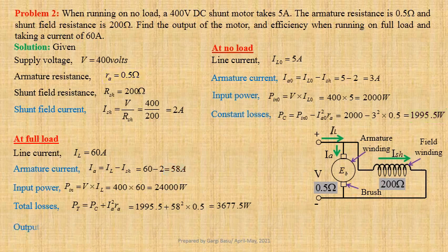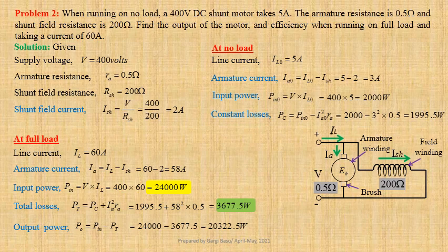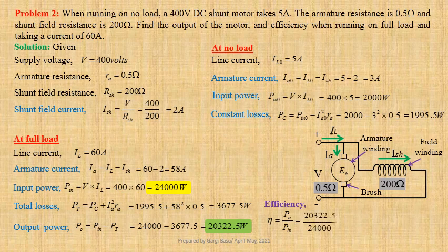Output power PO equals PIN minus PT, that is 24,000 minus 3677.5, giving us 20,322.5W. Efficiency of the motor eta equals PO by PIN, that is 20,322.5 divided by 24,000, giving us 0.8468 per unit or 84.68%.